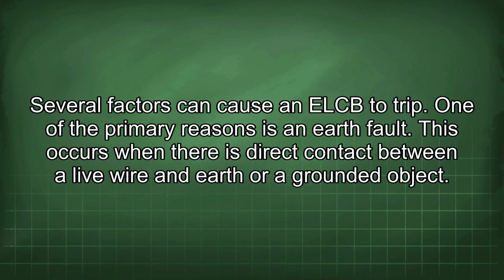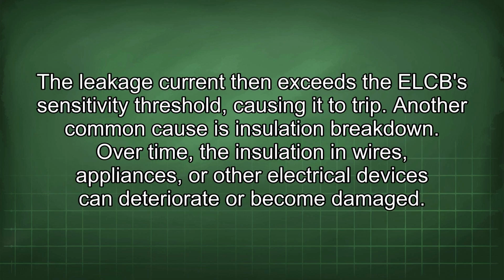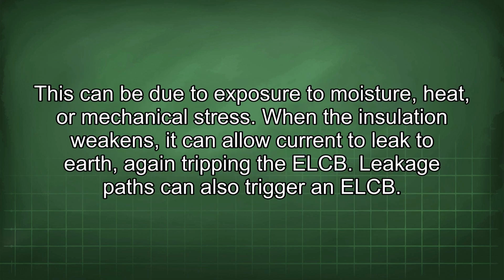One of the primary reasons is an earth fault. This occurs when there is direct contact between a live wire and earth or a grounded object. The leakage current then exceeds the ELCB sensitivity threshold, causing it to trip. Another common cause is insulation breakdown. Over time, the insulation in wires, appliances, or other electrical devices can deteriorate or become damaged. This can be due to exposure to moisture, heat, or mechanical stress. When the insulation weakens, it can allow current to leak to earth, again tripping the ELCB.